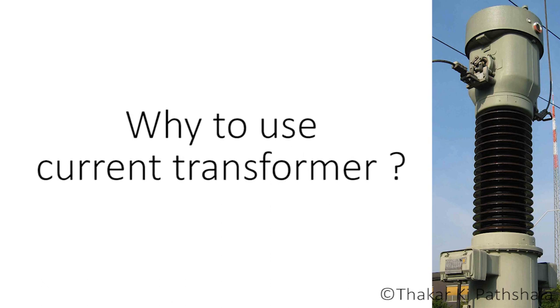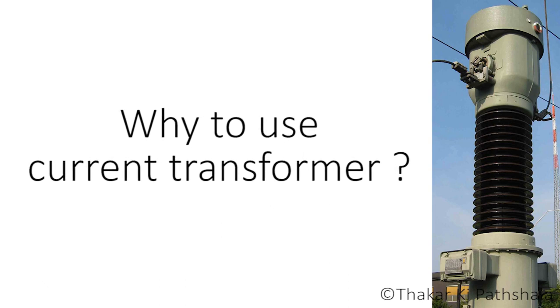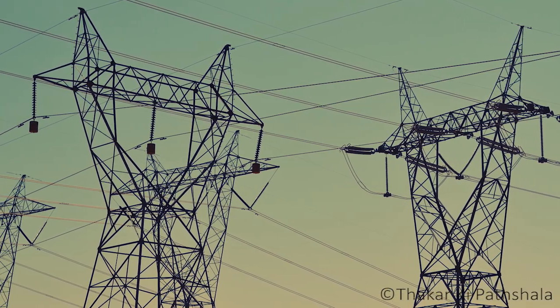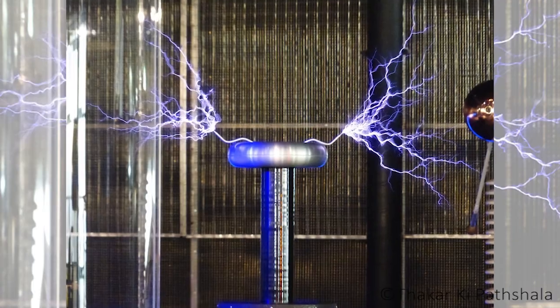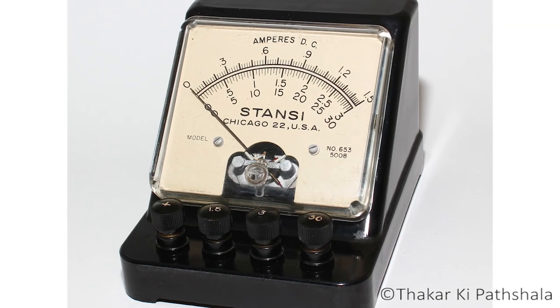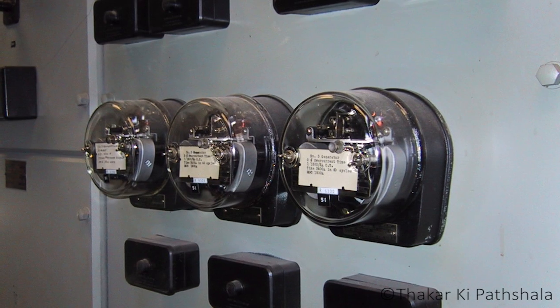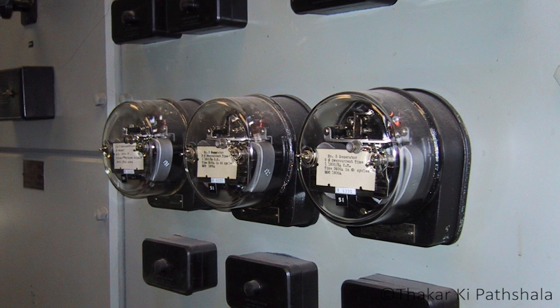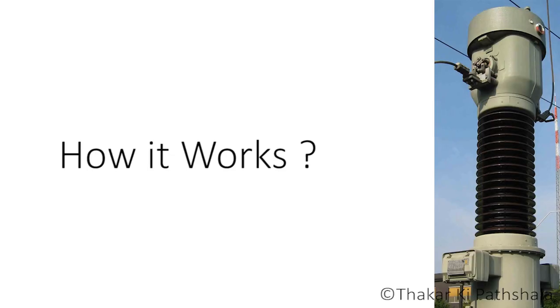Now another question comes to mind: why on earth do we need to step up or step down current when we are already stepping up and down voltage and are totally fine with it? We need to do this because whenever we are working with very high power lines, the associated current is very high, and our normal meters and protective relaying circuits simply can't handle that much current. So in order to measure high current and to use different relays, we need to step it down.